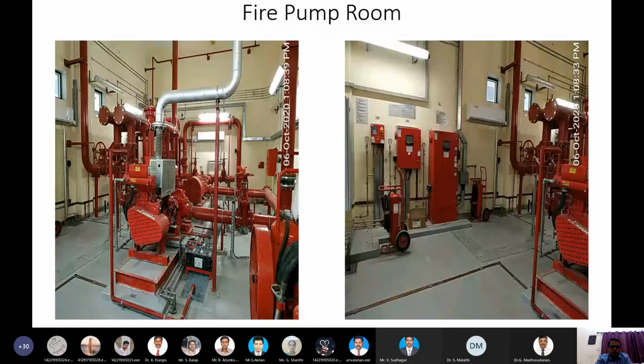This is the fire pump room. The sprinkler system is completely controlled here, and the fire pump room has three pumps - one jockey pump, one electrical pump, and one diesel pump. These pumps are connected to the delivery systems to support the sprinklers for the transformers and IDTs. The jockey pump automatically runs in case anything goes wrong with the transformers, IDTs, or any interconnected system. If the jockey pump fails, the electrical pump runs over, and if power supply is cut off, the diesel pump starts. There is a separate diesel tank nearby supplying the DG so the water supply for emergency sprinkling systems is not cut off.